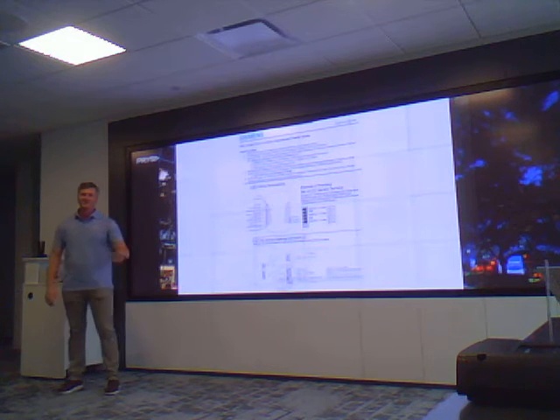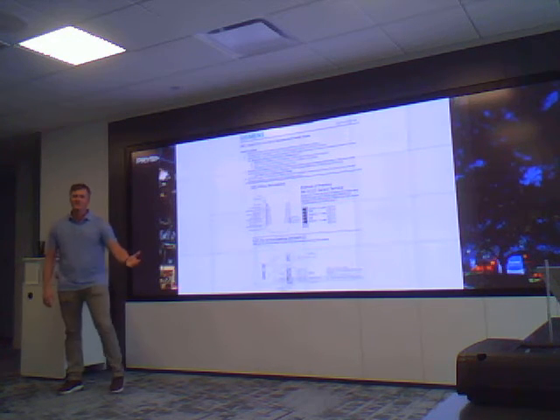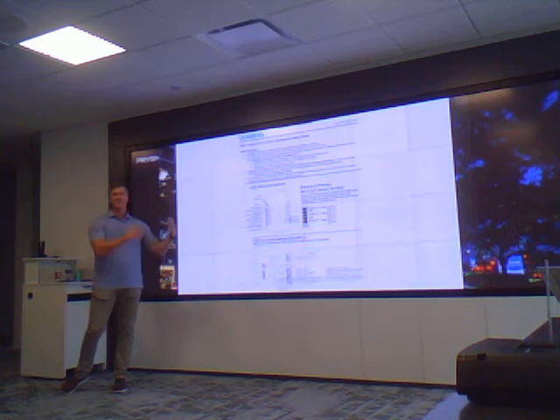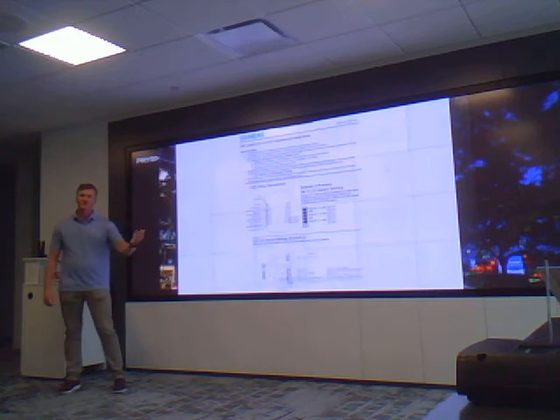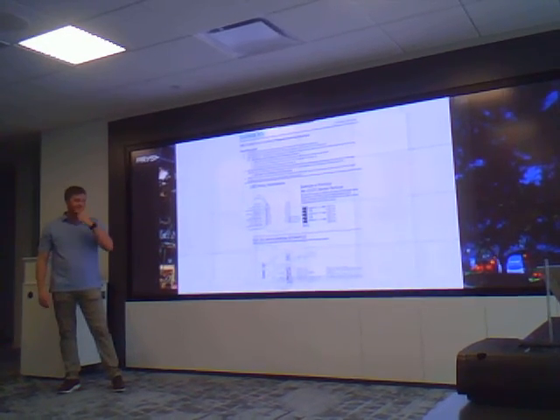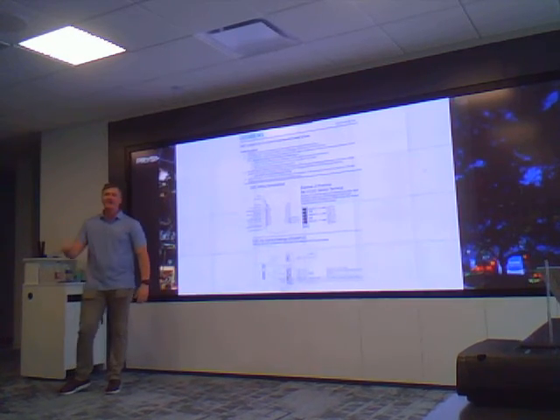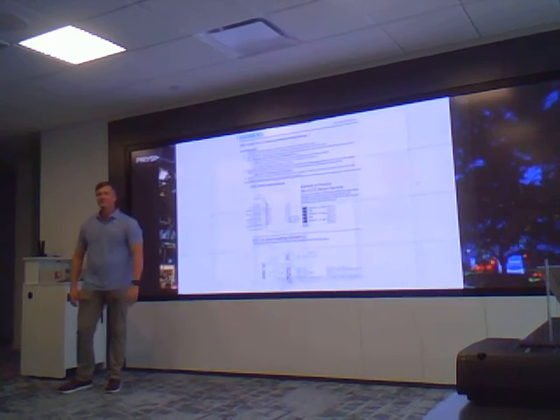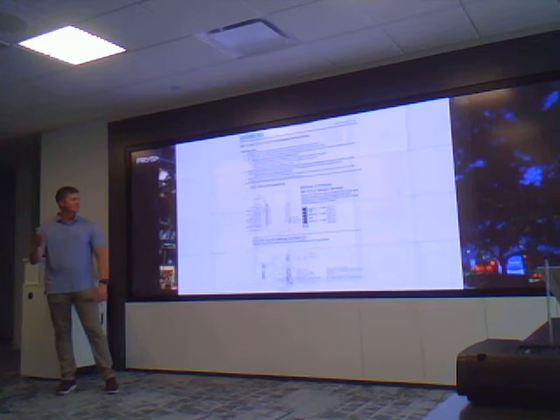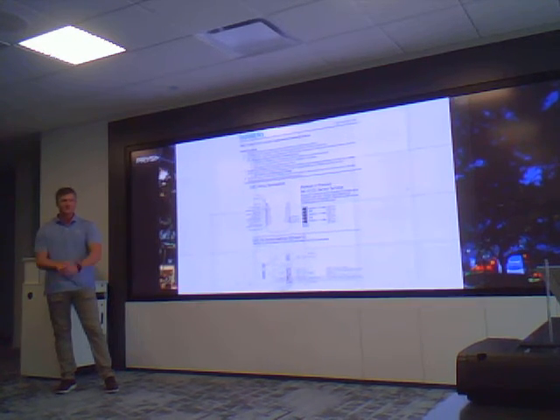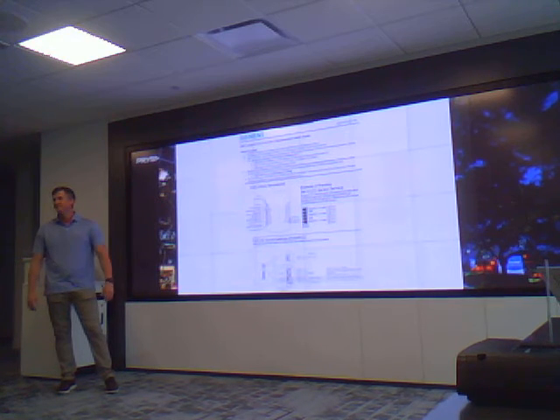So it's always still good to look, even though that falls under their scope, making sure our panel is okay and wired correctly. Usually it's a quick look, you'll see the blue or the black, and then you'll see the neutral and the ground. So it's little things like that, because they make mistakes too. And I don't want to flip that breaker on. I mean, it should just trip and flash, but you know, I never know.